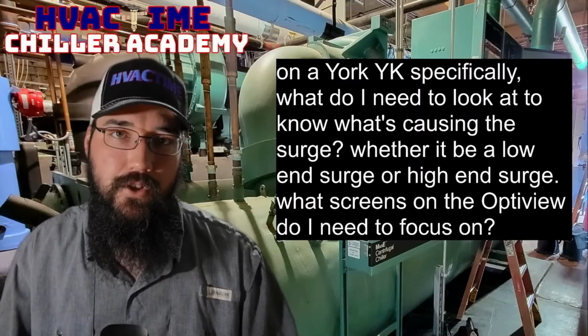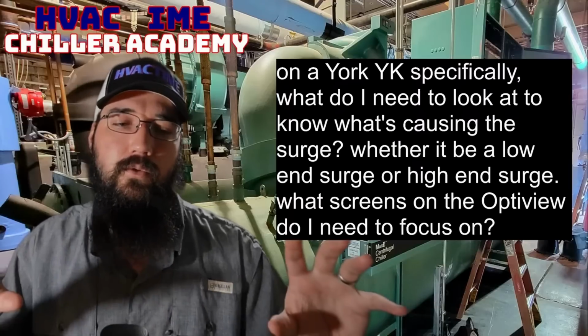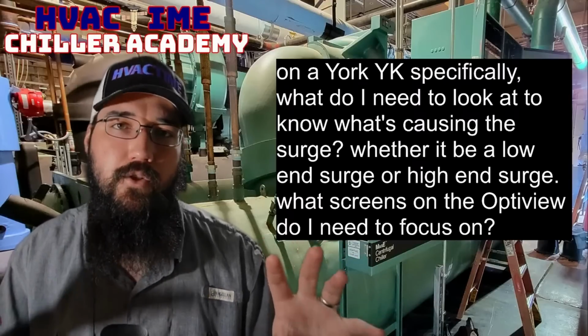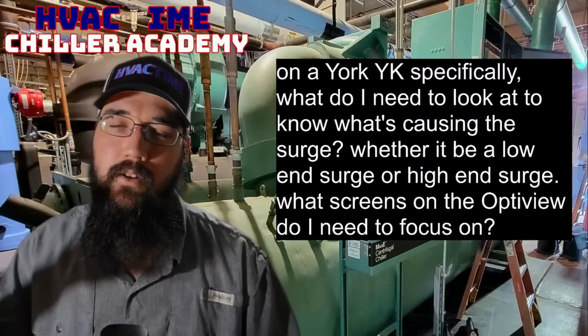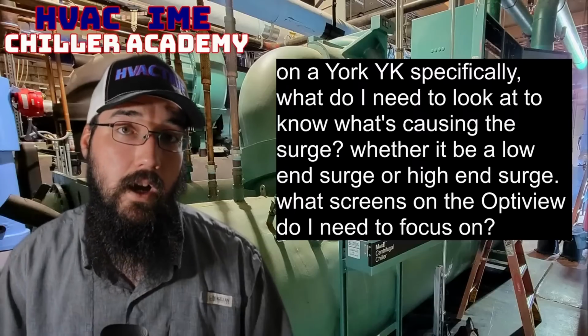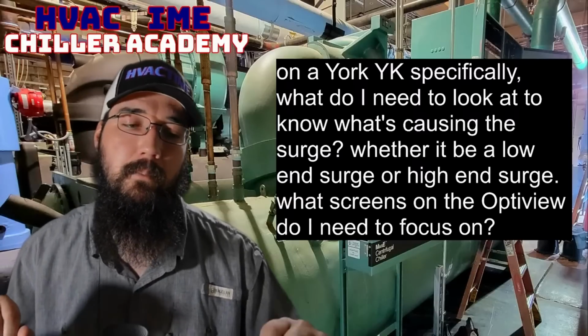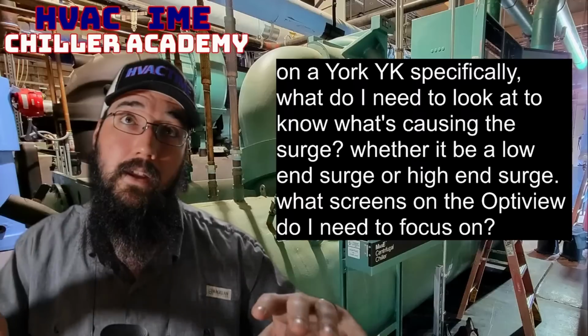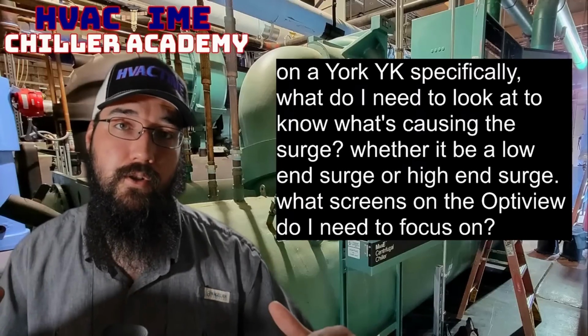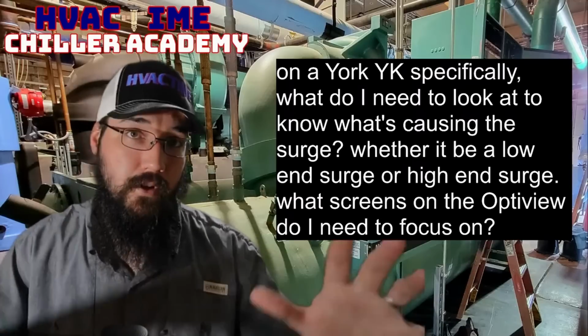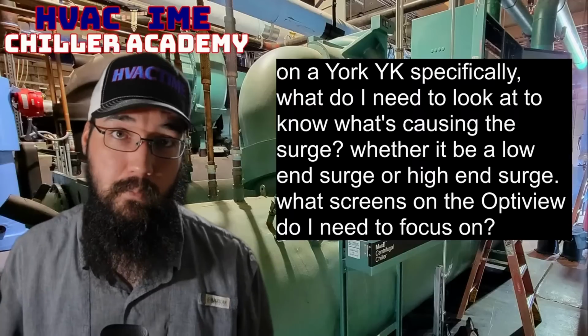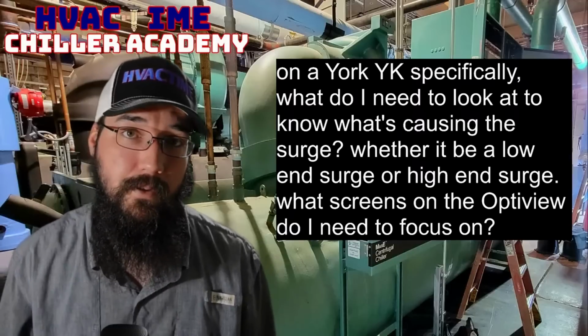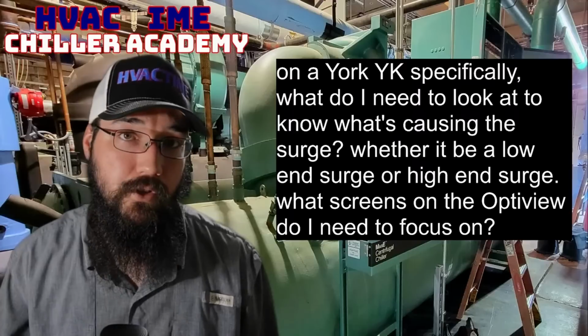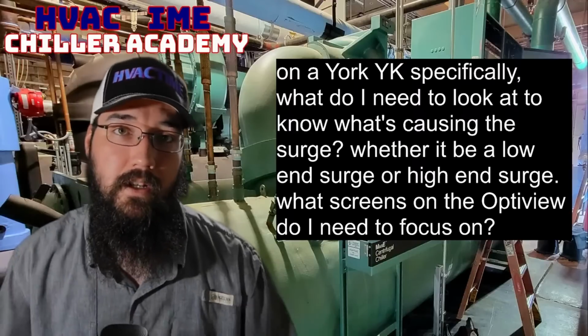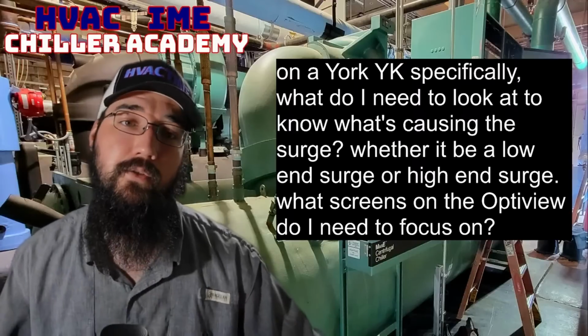A lot of surging does come down to, is your flow right? Is your load right on your evaporator? You're not running too high on the condenser. Is your charge where it needs to be? Now, you put all these factors together. Let's say all these things were perfect. Okay, you had perfect GPMs, you had a perfect charge, which you can verify through the sight glasses and stuff and get a pretty good feel for it.